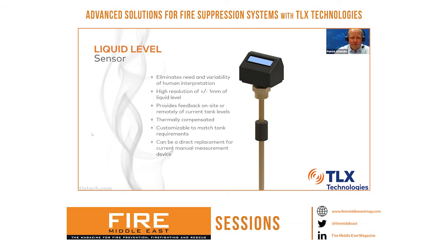The device itself can be thermally compensated. So we have a thermocouple that's inside the electronics, and if we work with a customer on a specific tank and clean agent, we can basically create a calibration table so that when the sensor is reading a specific distance at a specific temperature, it knows the weight. So the thermal compensation has been something that customers have asked about.